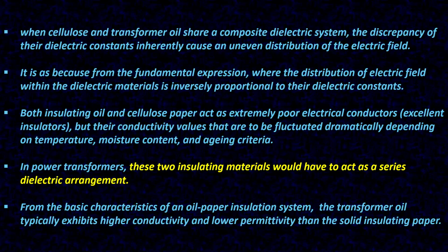Both insulating oil and cellulose paper act as extremely poor electrical conductors, excellent insulators rather, but their conductivity values fluctuate dramatically depending on temperature, moisture content, and aging criteria. In power transformers, these two insulating materials act as a series dielectric arrangement. From the basic characteristics of an oil paper insulation system, the transformer oil typically exhibits higher conductivity and lower permittivity than the solid insulating paper.